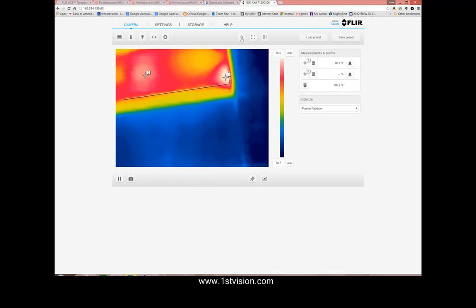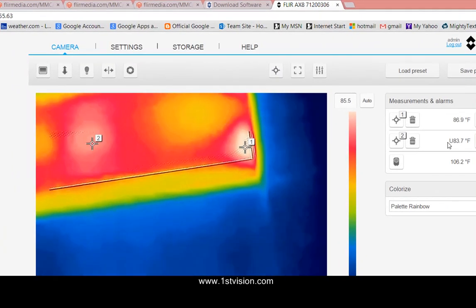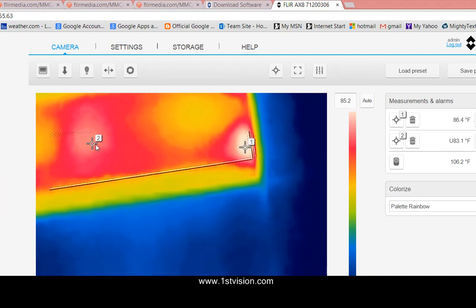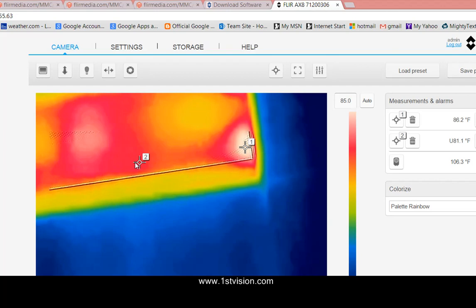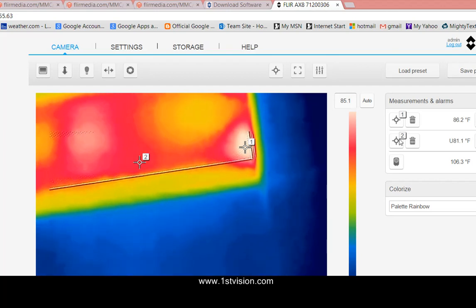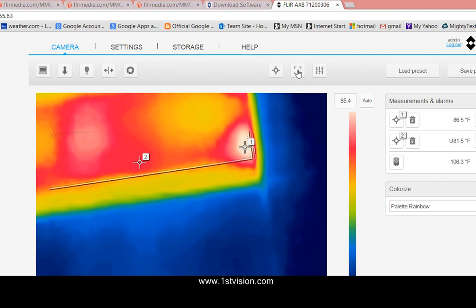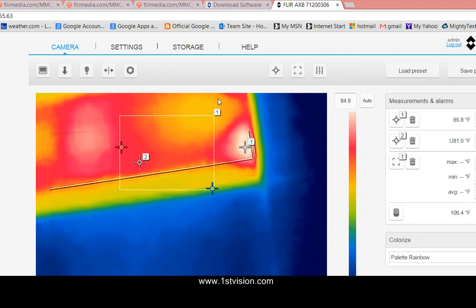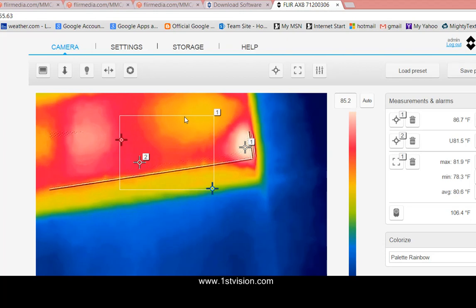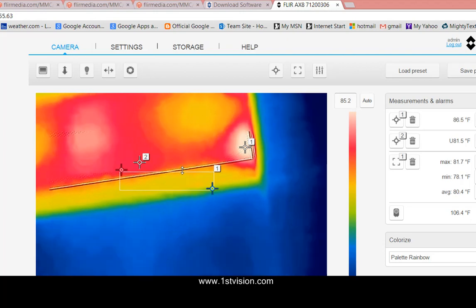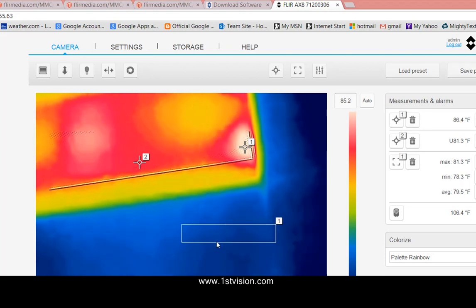Here's where you really need to use the camera. Now this will put up spot measurements. So this just put up a second spot measurement here. You can see and you can drag this to wherever you want. So over here now we have two spot measurements with two temperatures. The little box draws you a box which of course you can change the size of if you want and you can move it.